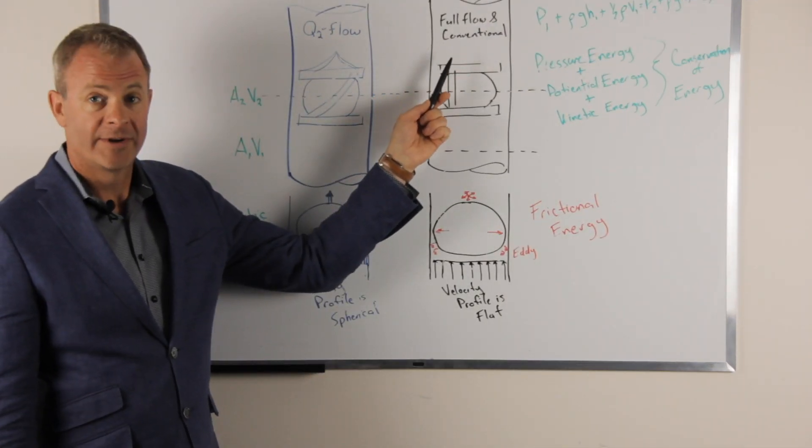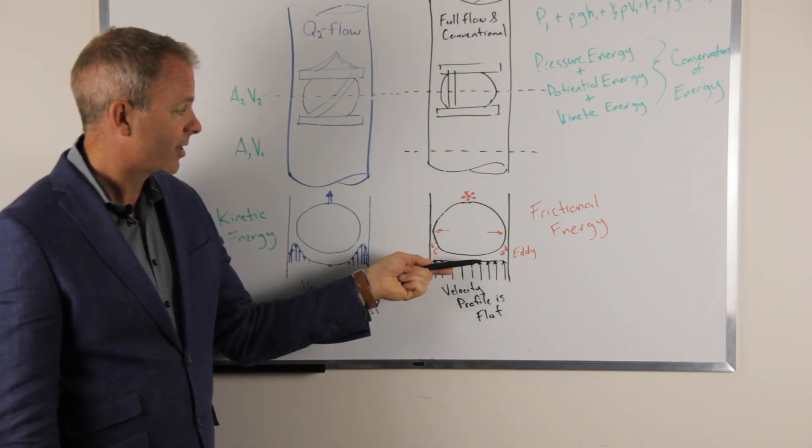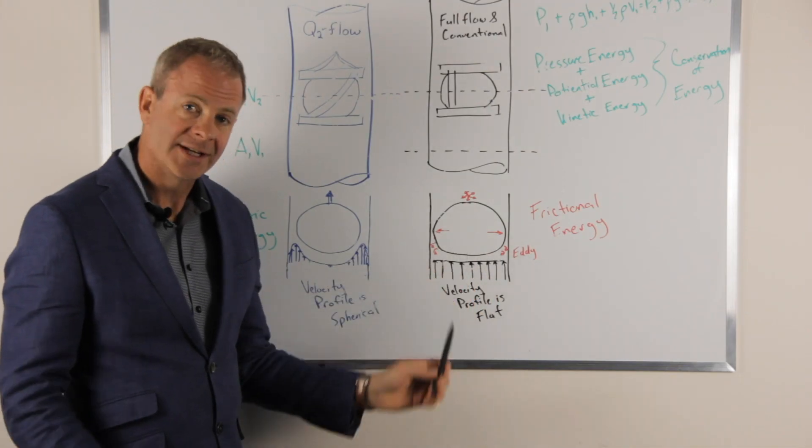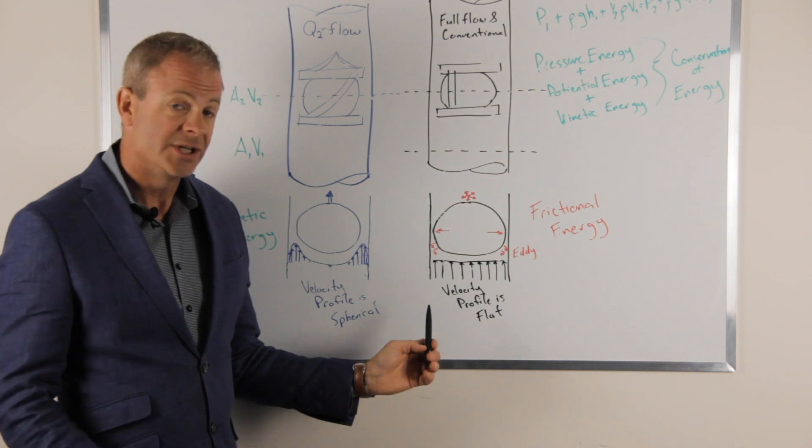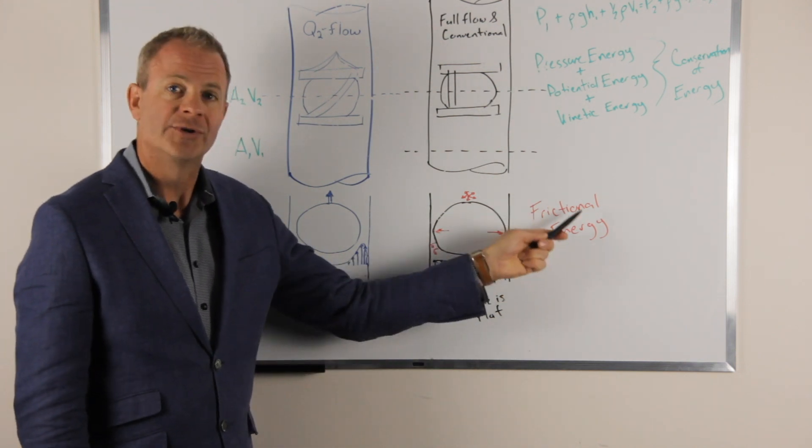With full flow cages and conventional cages, they have a flat velocity profile that comes up and the ball vibrates back and forth. One, that causes little eddies that cause pressure drop, which decreases your flow. Two, it causes a lot of frictional energy in your pumps.